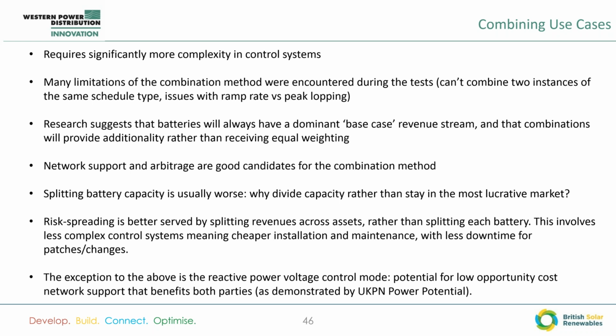However, we have a scenario where, for instance, the solar park is generating 800 kilowatts and we've constrained it to 500. The battery is able to hold it at 500 kilowatts, but then the solar level drops and the ramp rate control goes, the solar level is dropping, I need to increase my export to offset that. Well, actually it doesn't, because the first use case, the peak lopping, is already holding it stable at 500. So until it drops below 500, the other use case shouldn't do anything.